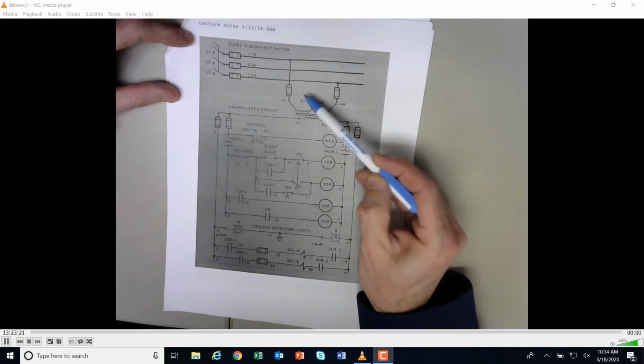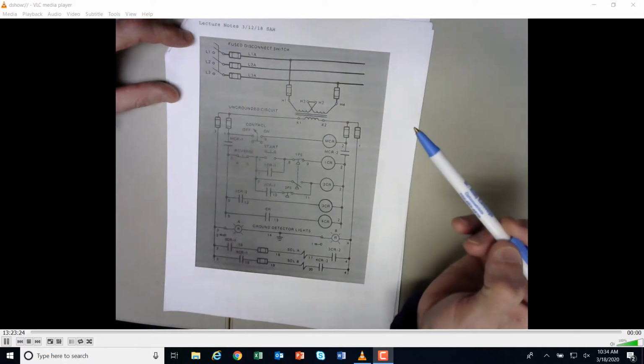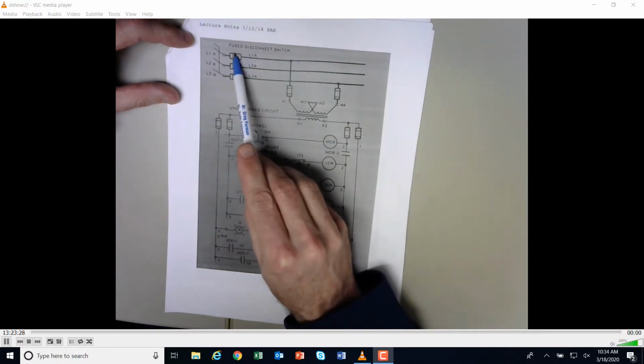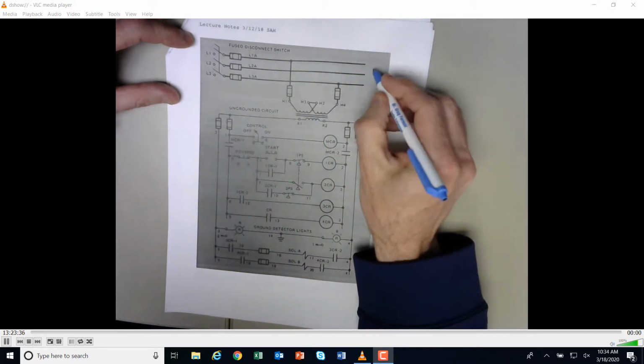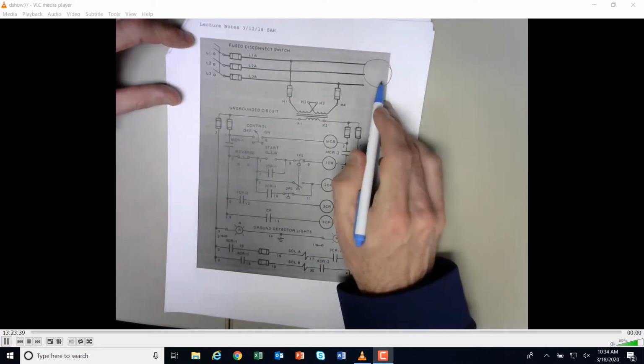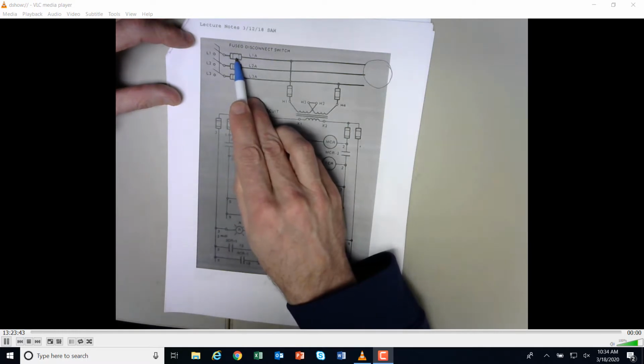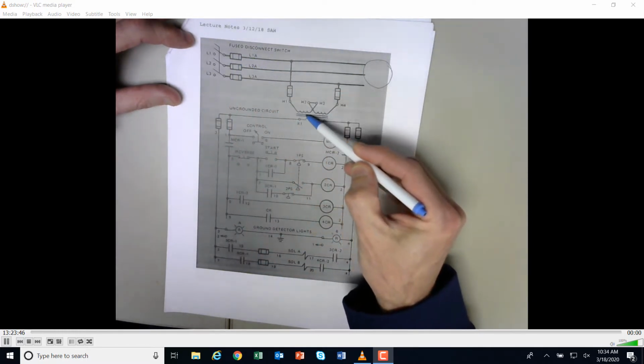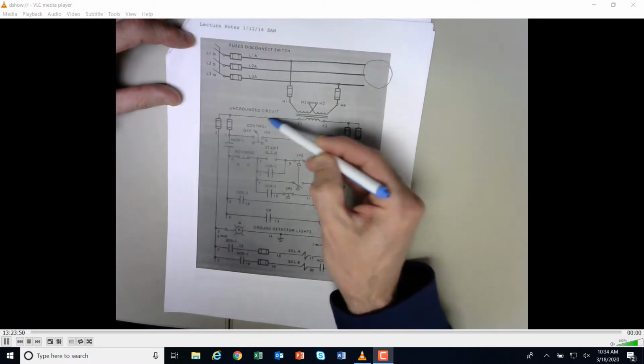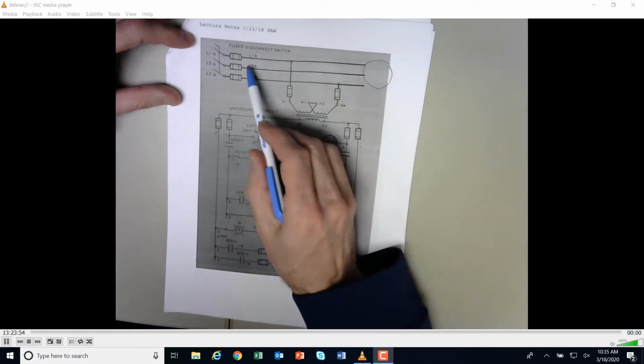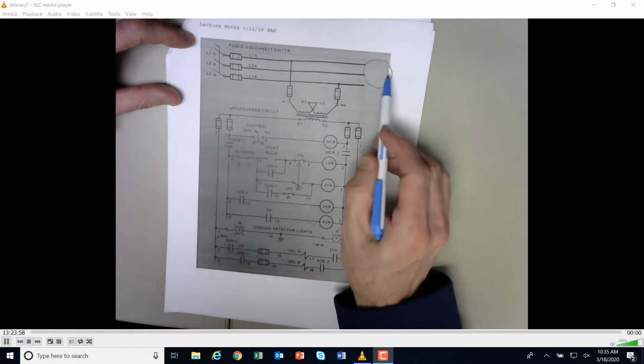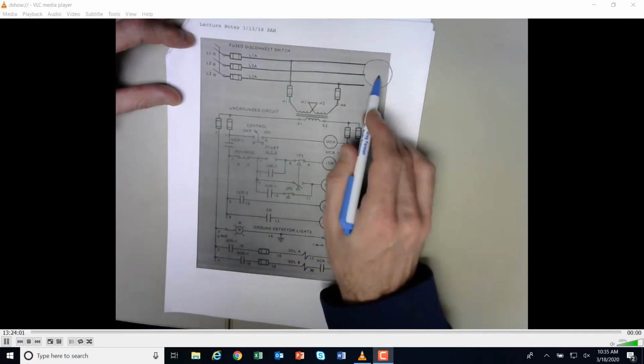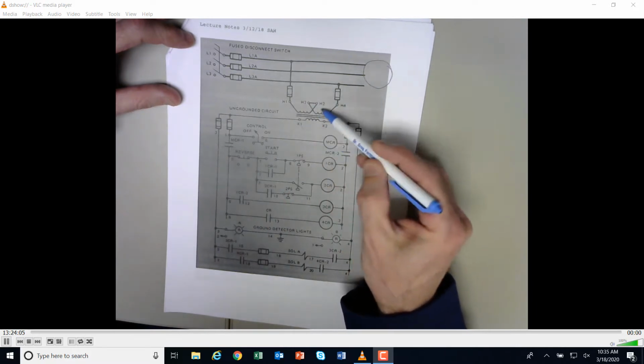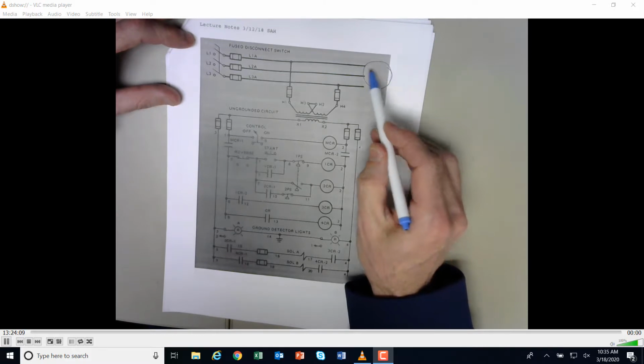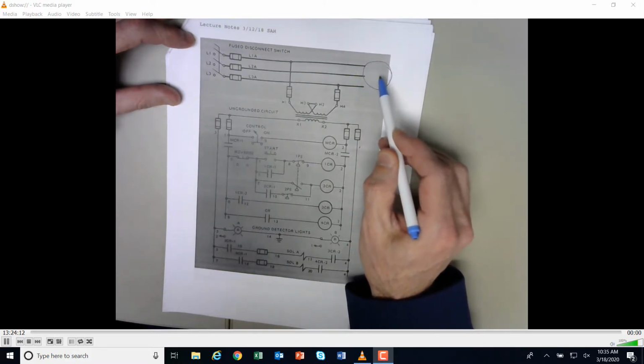And then we have fuses that are going to our transformer. So let's first of all take a look at these. If for some reason this fuse blew, and this fuse could blow for a number of reasons, most likely it would be that somewhere over here the load had an ampacity issue and it would blow that fuse. Well, if this fuse blows, then the line to the transformer is going to go down, which means that this whole circuit down here is going to go down. So blowing L1 or L3 here is going to bring not only your load down, likely making it into a single phasing situation, but it's going to take the transformer down, which is going to take the control circuit down, and because this would have main contacts in here somewhere, it's probably going to bring this down, okay?